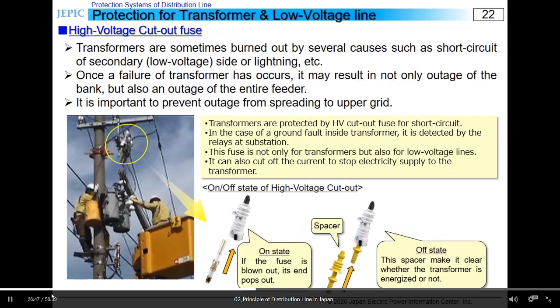Next is the protection for transformer and low voltage line. Transformers might be burned out by various causes such as lightning, short circuit of low voltage line, and so on. A burnout transformer might cause an outage of not only the customers connecting to the transformer, but also the entire feeder. So it's very important to prevent the outage from spreading to upper grid.